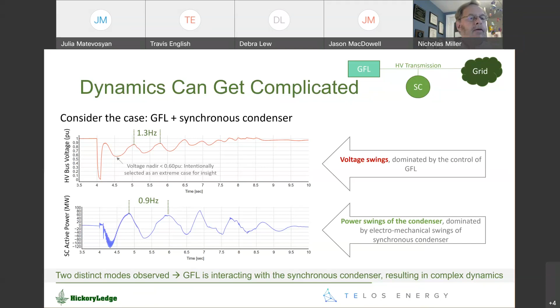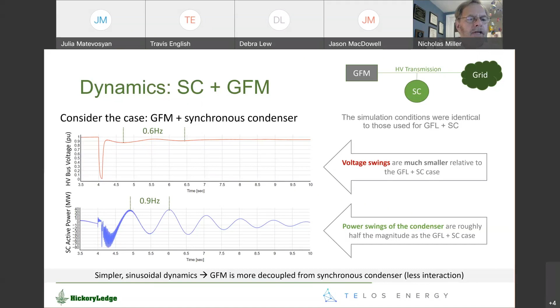If we look at the next slide, please. This is a similar condition. We see the condenser still swinging around, rather poorly damped at the bottom, but with minimal interaction with this version of the grid forming converter. So we were pretty excited about that, but it's still not clear whether that's just control or whether there's something intrinsic. So, next slide.